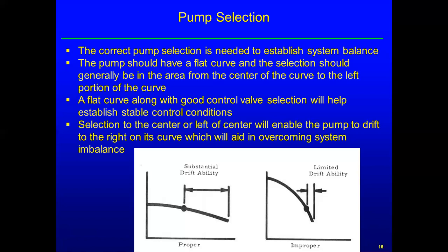Also, there's the steepness of the curve, for any change in flow, if it's a reduction in flow, and you're not doing this with speed control. Now, these slides don't really consider speed control, and we'll have another presentation later that will bring that more fully into the discussion. With speed control, the shape of the pump curve is not nearly as important as it is with constant speed pumps, but you need to know both sides of the argument.